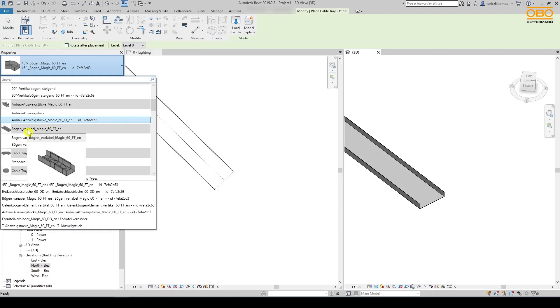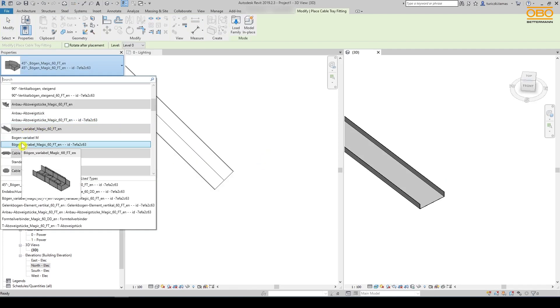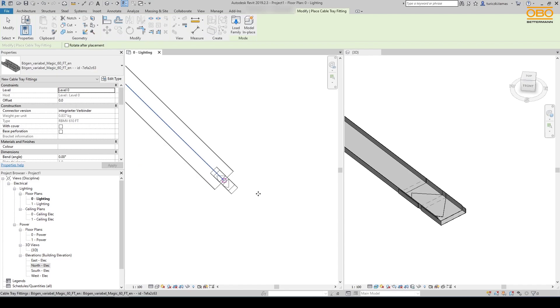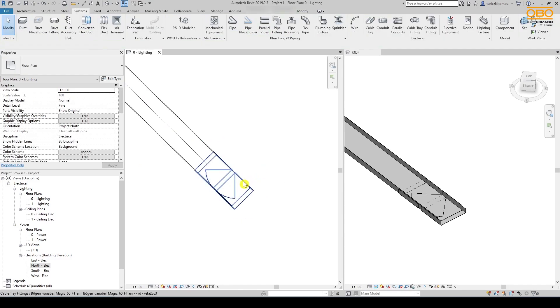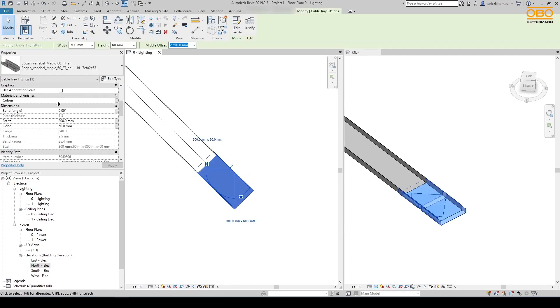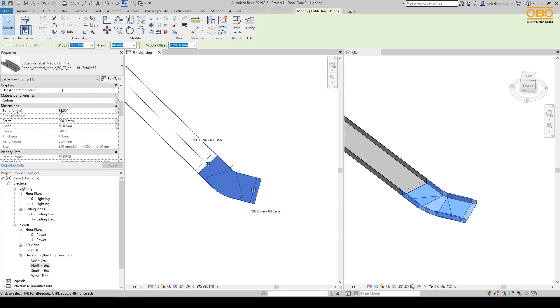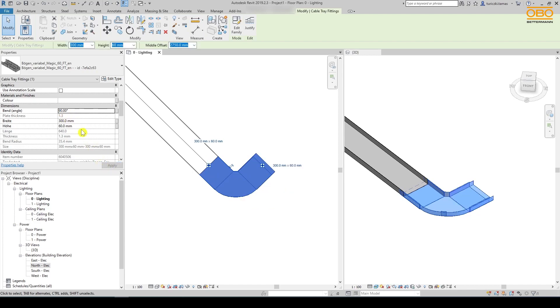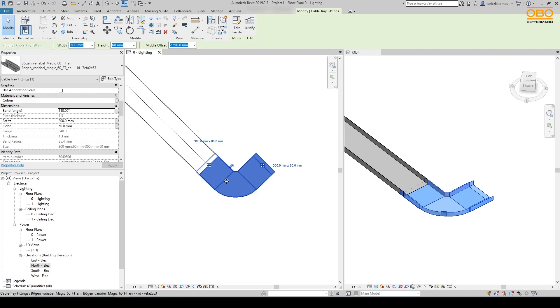The placement of the variable bend is similar to the 45 degrees bend. Here we have the possibility to set the angle between zero degrees and 90 degrees under dimensions and bend, just like in reality. To prevent incorrect planning, the input of an angle above 90 degrees is not accepted. The bend simply stops at 90 degrees.